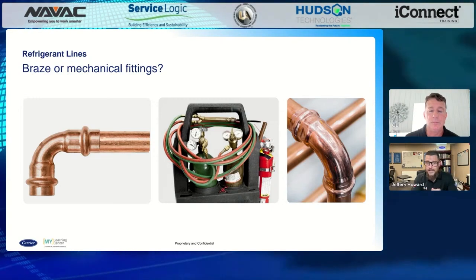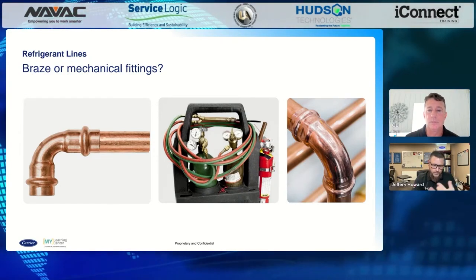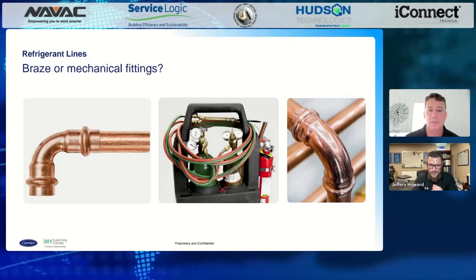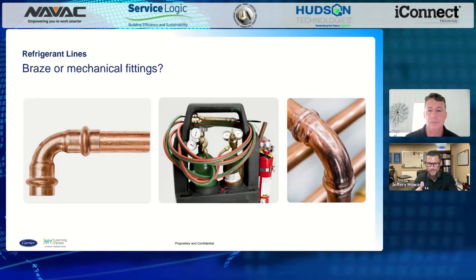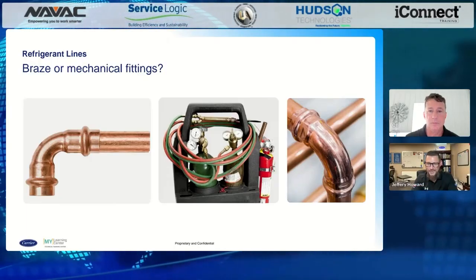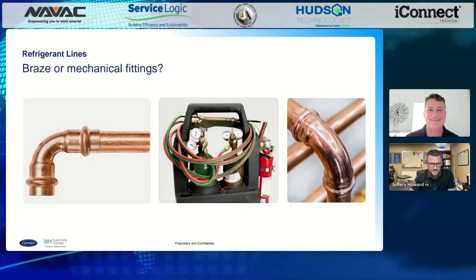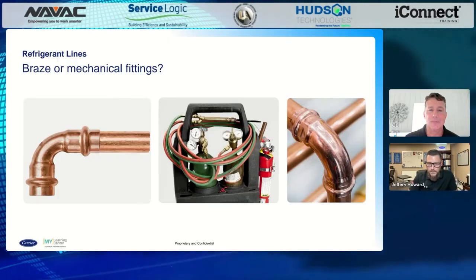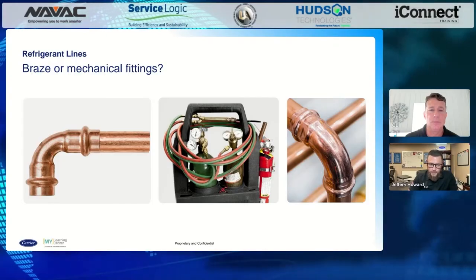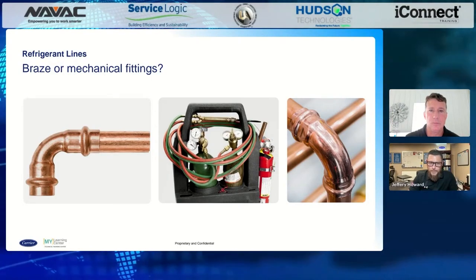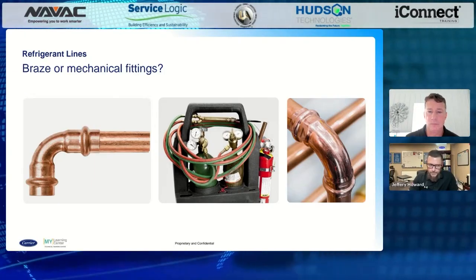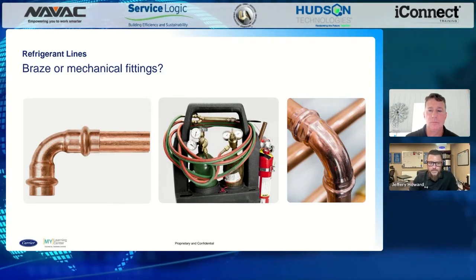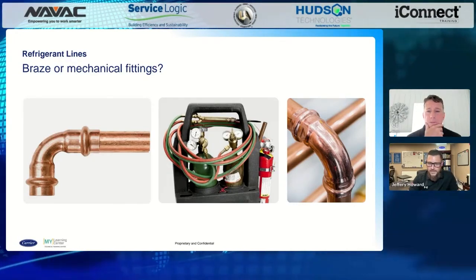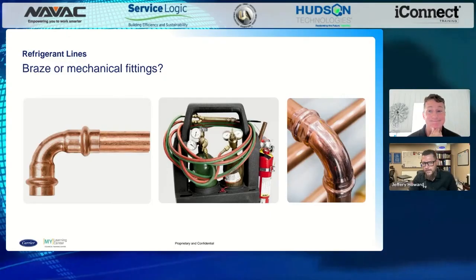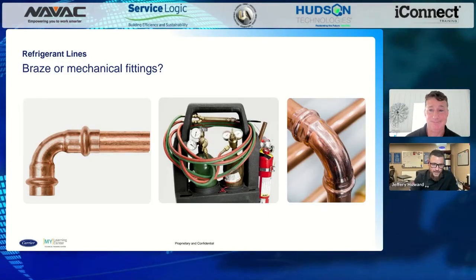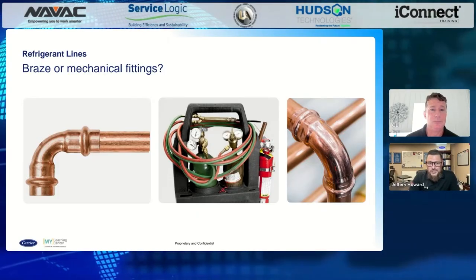You want to make sure that you're taking care of the lines. When you go to deburr and cut them, you're actually using a piping cutter, not a rigid blade or Sawzall that you may have in your truck. You want a nice round cut with the piping cutter. Make sure you clean them and wipe them down to keep moisture out. Follow your instructions on your tools if you're using any press or push mechanical fittings. With brazing, it's the same thing—best practices, as a colleague of mine said, haven't changed in decades.